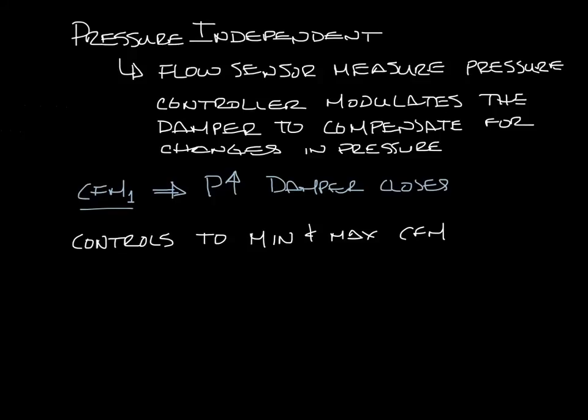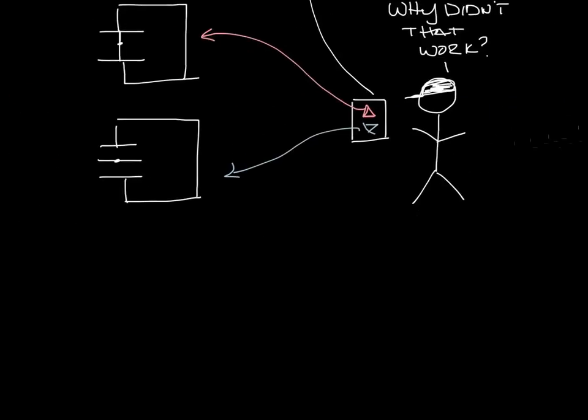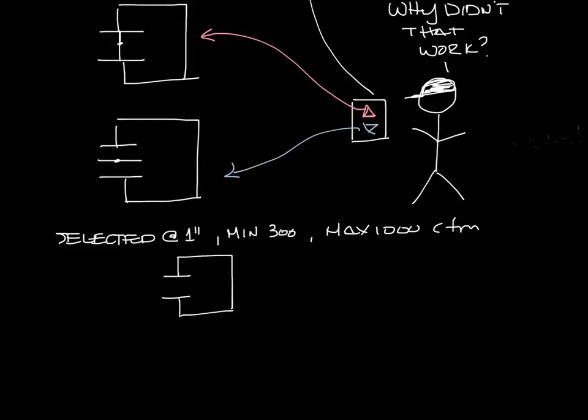So let's go back to our guy in the field. Let's say the VAV box was selected with 1 inch of inlet pressure, a minimum CFM of 300 CFM and a maximum of 1000 CFM. In a perfect world, you'd have 1 inch inlet on the box in the field and you would get your minimum CFM when the damper is almost full closed and you would get your maximum CFM when the damper is almost full open. I'll get to why it's almost full open in a minute.